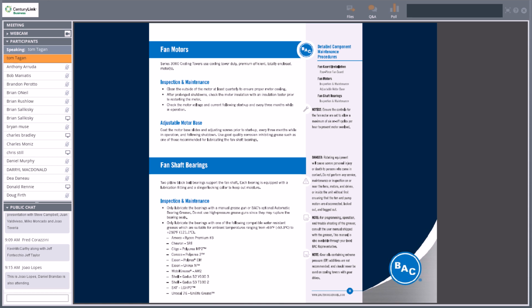Again, fan motors, and talking about fan lubrication, the importance of lubrication of the fan shaft bearings. They recommend only lubricating the bearings with a manual grease gun or the BAC's optional automatic bearing greaser. A little propaganda. I think everyone offers that automatic bearing greaser. It is a pricey item. Typically, we extend the lubrication lines and we see the bearings lubricated manually. Again, it lists the manufacturers and the type of lubricants that are recommended.